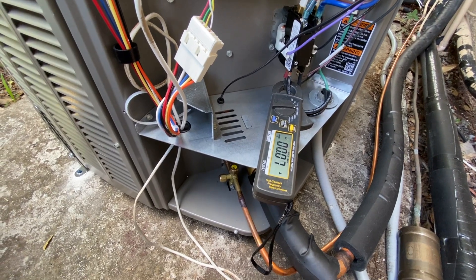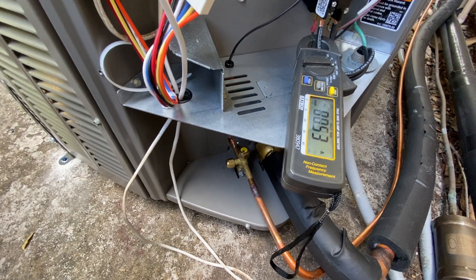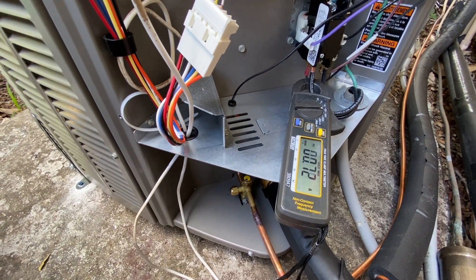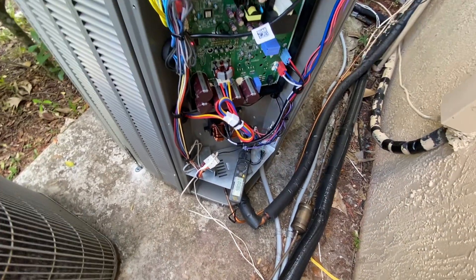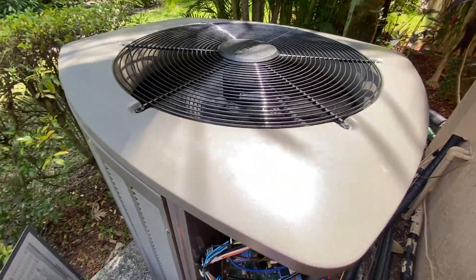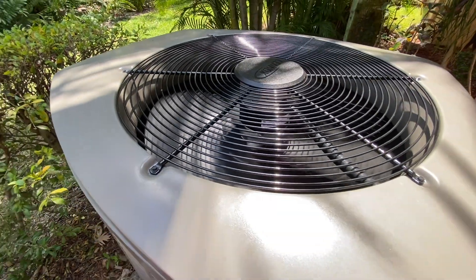On this particular scenario, the unit is coming online — it was off for a while after cooling the house and now it's coming on at a slower speed, running at variable speed and trying to catch up to see where it stabilizes. The amps are slowly creeping up and even the top fan is running very slow, not much noise at all.